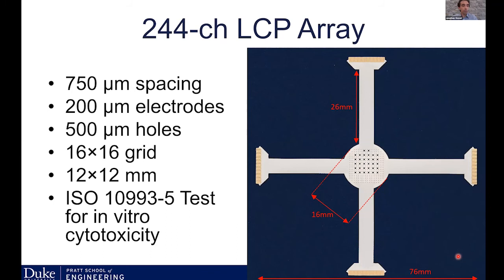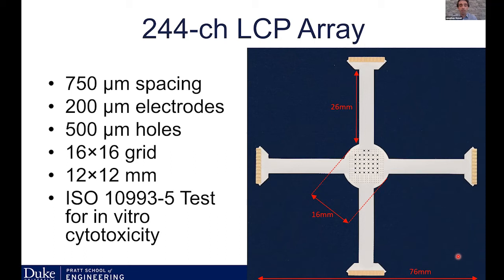Next, we worked on scaling up the technology. We want to see if we could build larger electrodes for use initially in non-human primates and then in humans. We made an array of 244 electrodes with 750 micron spacing, incorporating holes for simultaneous recording with penetrating electrodes. A nice property of this manufacturing process is that biocompatibility testing has already been done as part of the ISO 10993 standard, and we've done additional testing since then. We think the translational opportunity for this technology is high.